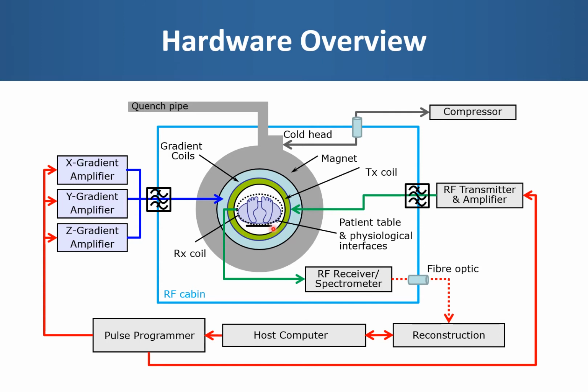Then we also have the patient table that moves the patient to the isocenter of the magnet where the uniformity is greatest. This table also supports physiological interfaces. For example, we may want to do a scan synchronized to the patient's ECG, so we can look at their heart, for example, or we may wish to synchronize the acquisition to the patient's respiratory motion so as to minimize artifacts from breathing. We also have a host computer where the MR scanner operator, the radiographer, enters the patient demographics and the required scan parameters.